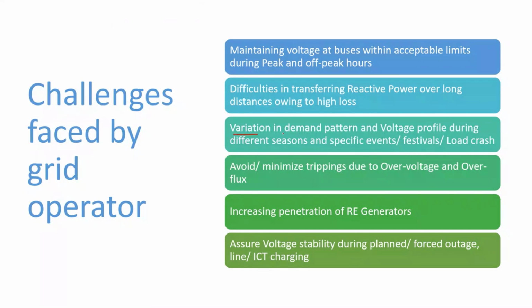Then the variation in demand pattern, voltage profile during different seasons, specific event, festival, load crash. Many of you have already discussed that throughout the day, the voltage pattern will be different. Demand pattern will be different. Depending upon that demand pattern, voltage profile across the different nodes will be different. And these voltage and demand patterns will vary according to different seasons, right? So you have seen that in the winter you are facing high voltage, while in the summer you face low voltage. Because in the summer the amount of load is high and in the winter the amount of load is low.